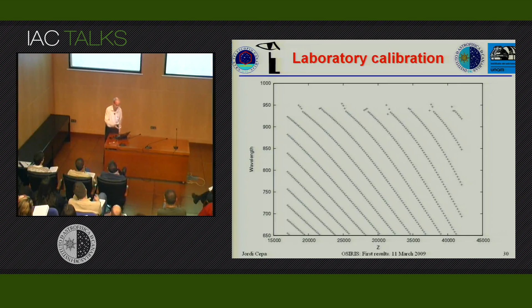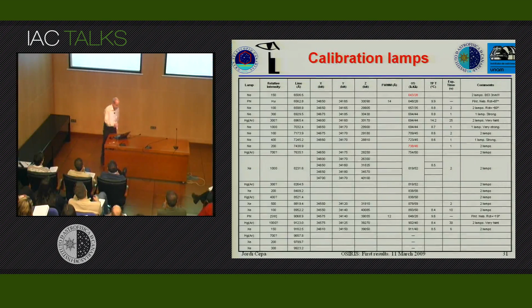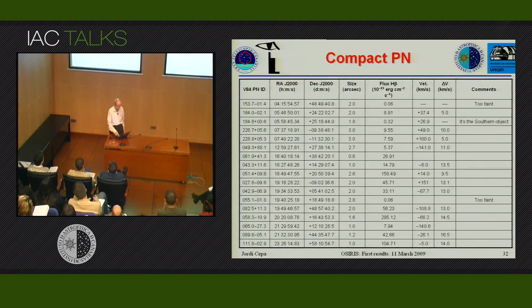Okay, this is a set of calibration lamps for the different full width half maximums and intensities that we are going to use. This is a catalog of compact planetary nebulae that can be used for calibrating your favorite emission lines. Summarizing the commissioning results obtained so far: the instrument is integrated in the GTC, the mechanisms are working, and we are working with the updated control release. Most of the imaging and spectroscopy tests are completed, and data reduction and analysis is underway. TF calibration is underway as well. We need to calibrate the tunable filter to check the calibration again. Instrument throughput is as expected, and the instrument has already been doing science verification proposals for 1 week, as I was told. 1 week? Yes, more or less 1 week.